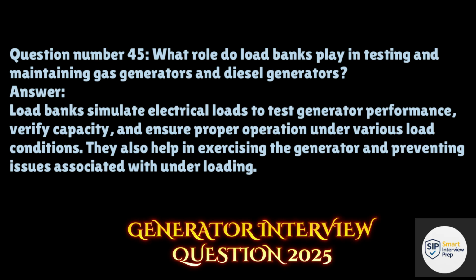Question 45: What role do load banks play in testing and maintaining gas generators and diesel generators? Answer: Load banks simulate electrical loads to test generator performance, verify capacity, and ensure proper operation under various load conditions. They also help in exercising the generator and preventing issues associated with underloading.